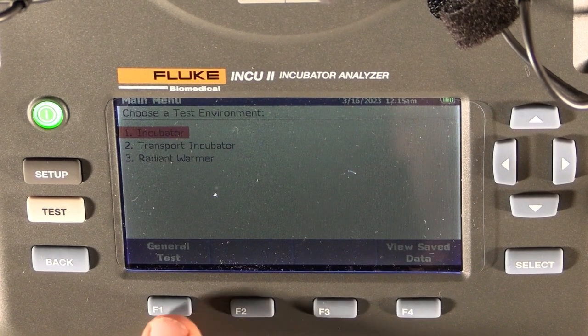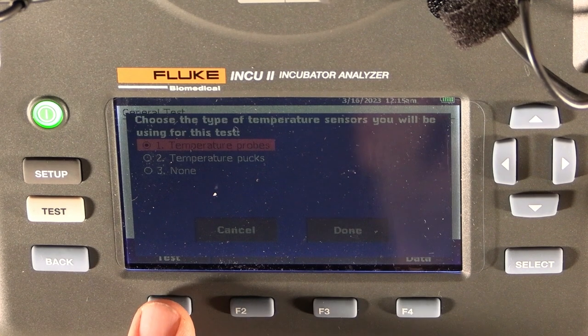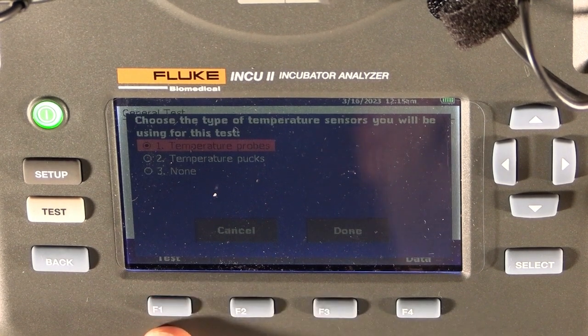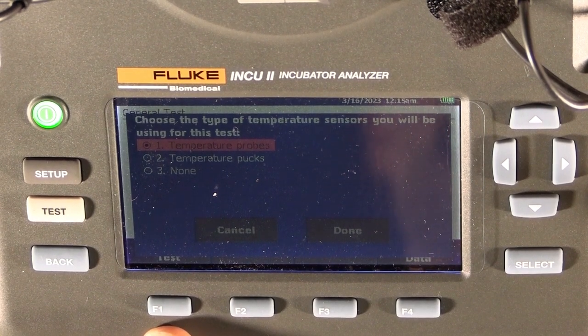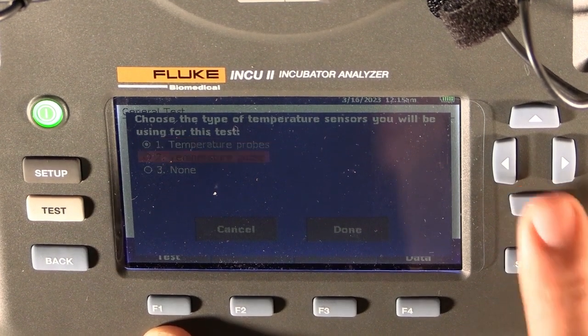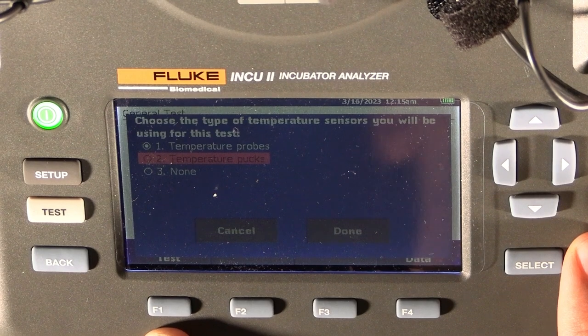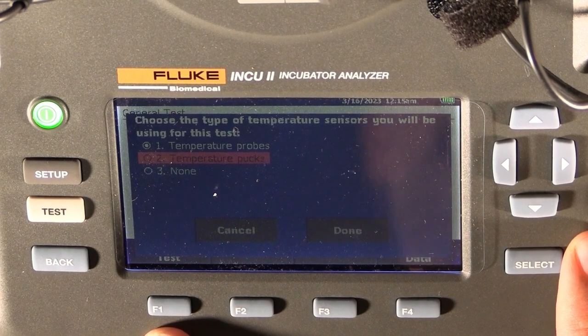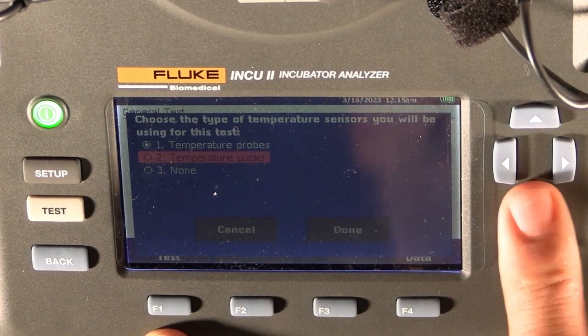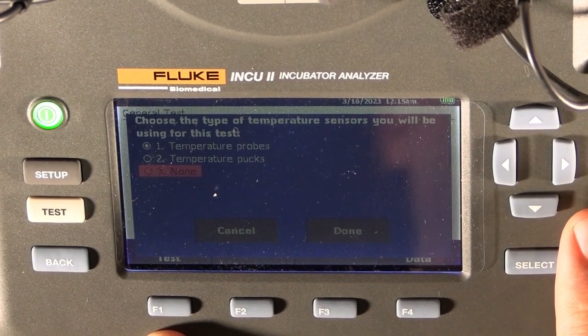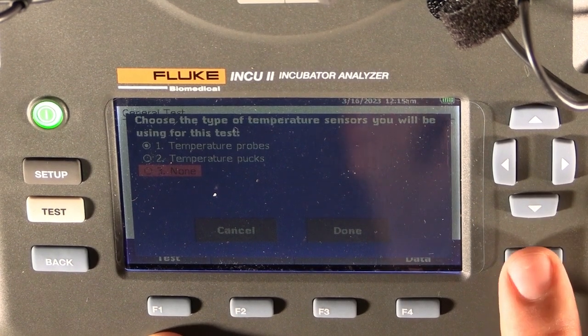then general test, that is where I choose what sensors I will be using to do this test. Now we have various sensors. We have the temperature probes, which we use for the transport and for the normal incubators, or we have the temperature pucks, which are these round metal temperature probes, which we use in the overhead warmers. Or if we're not going to do temperature, we're only going to use humidity or sound, then we just go to none.